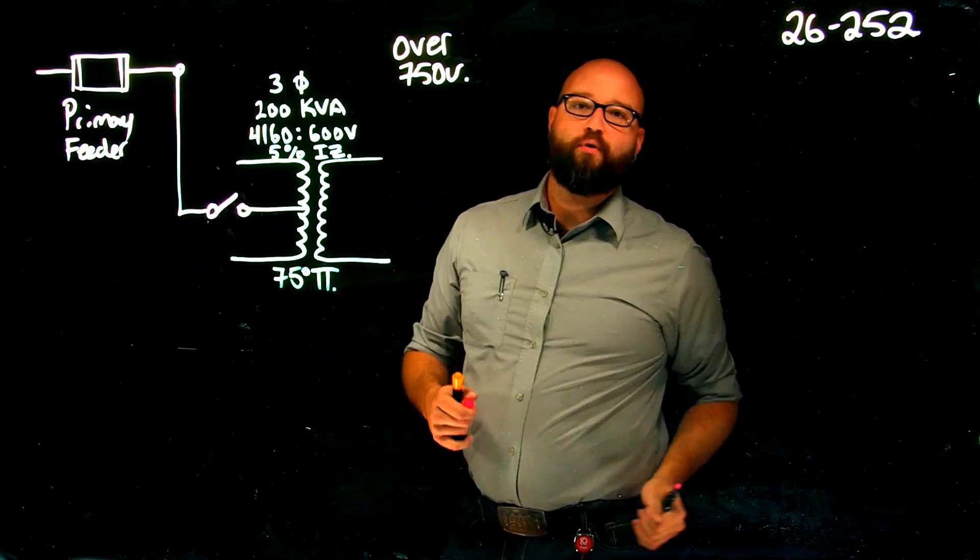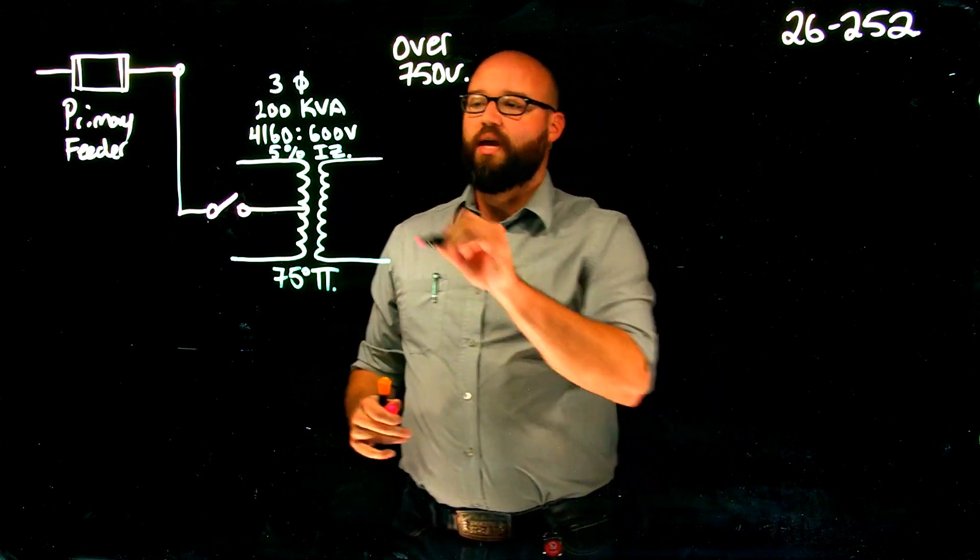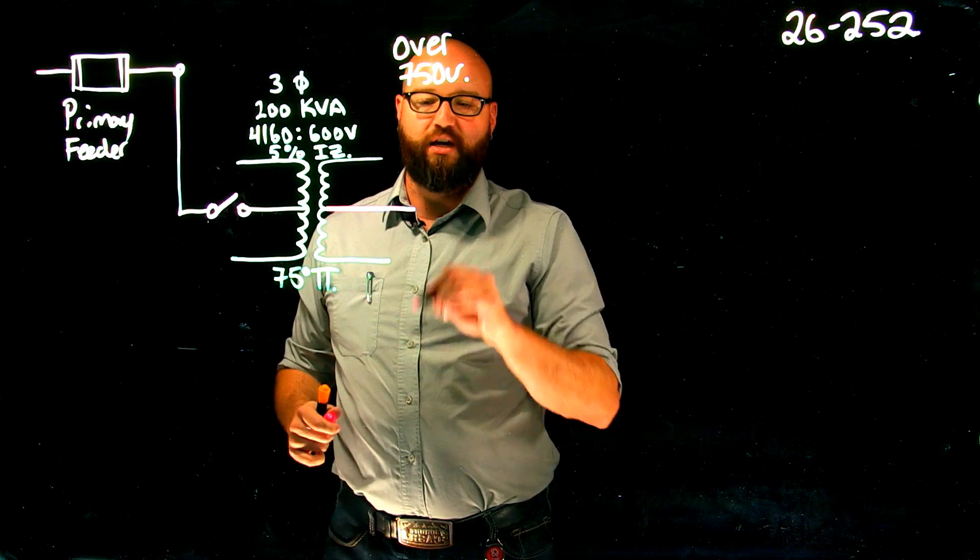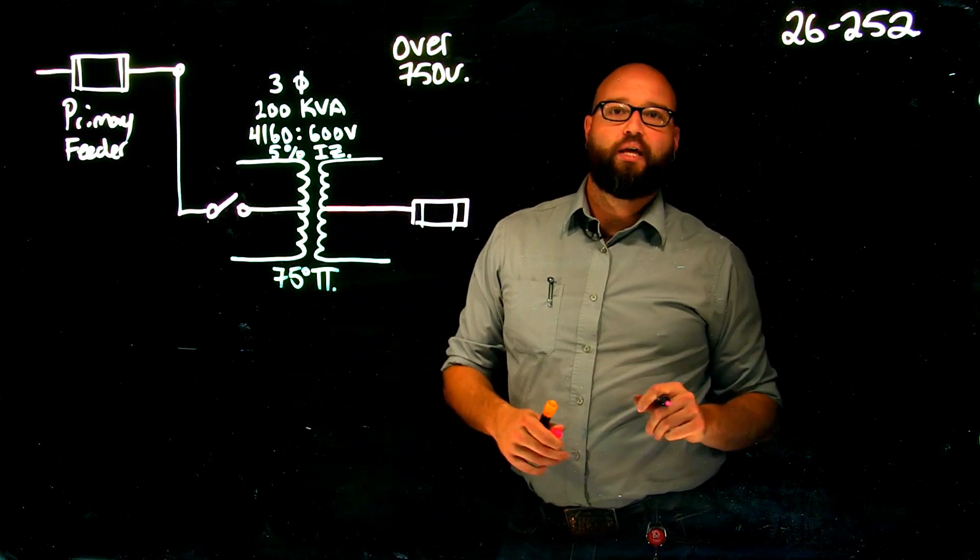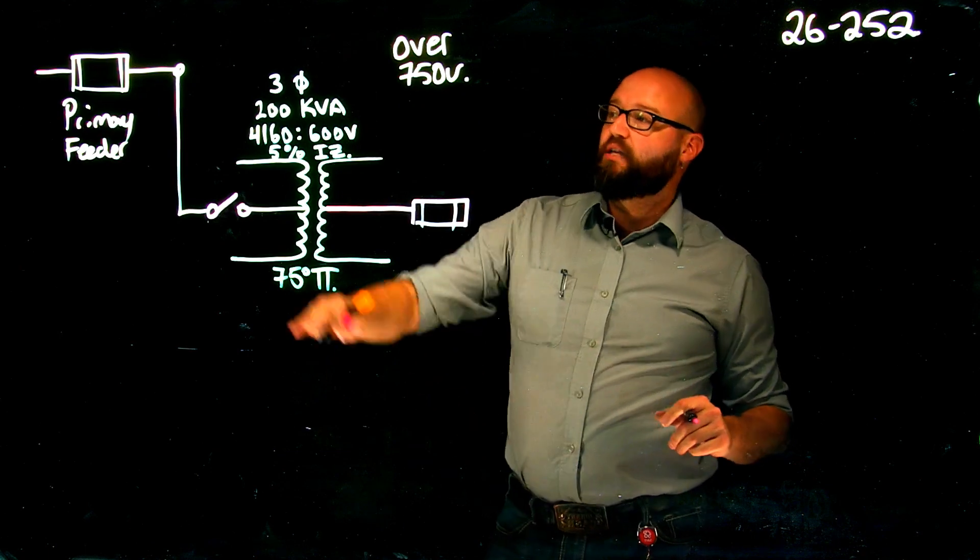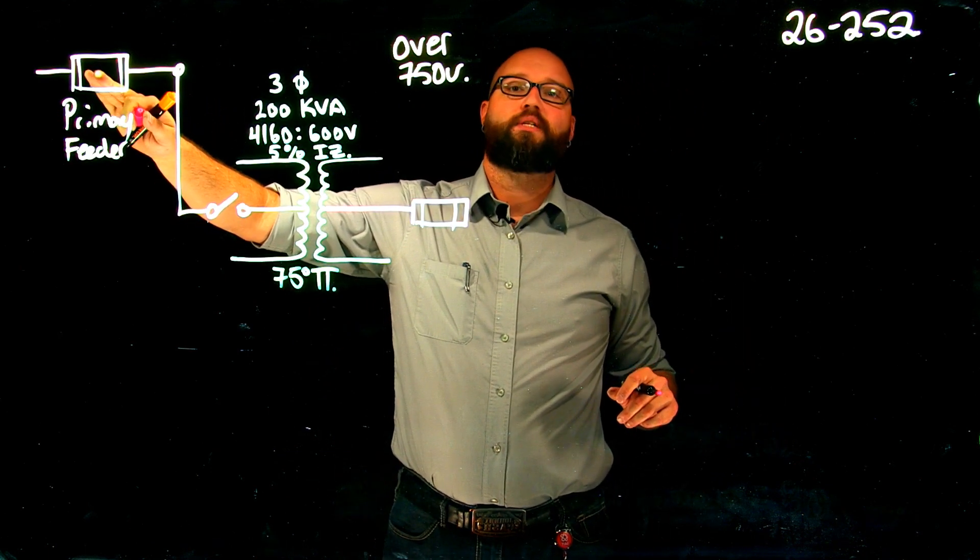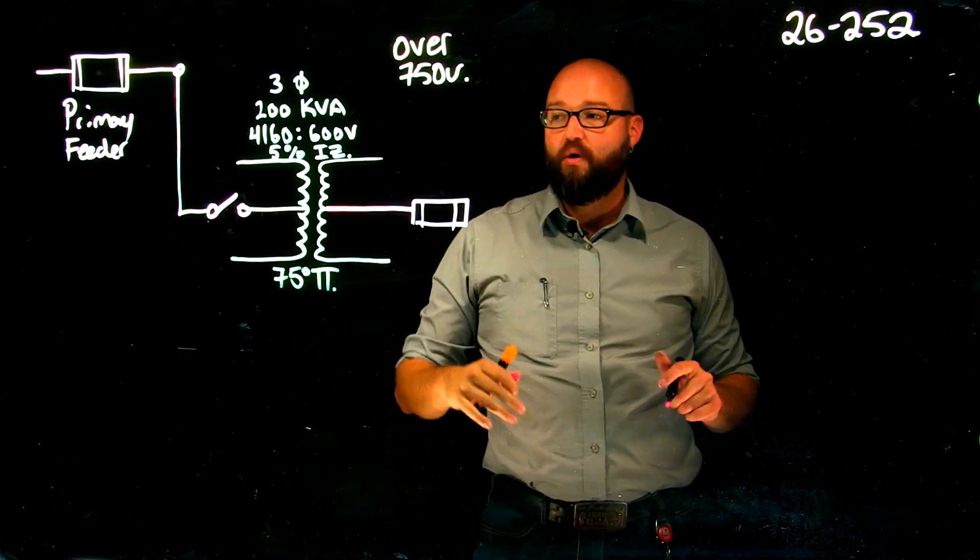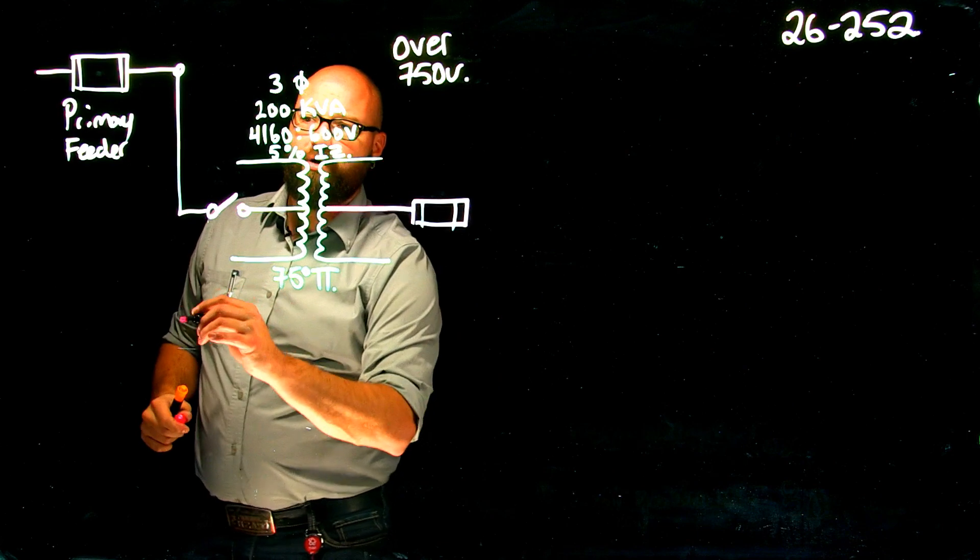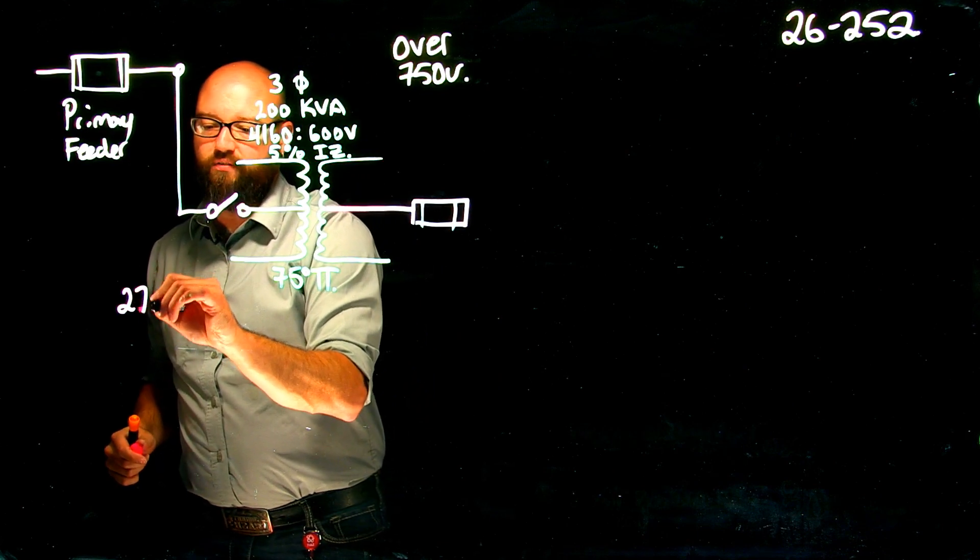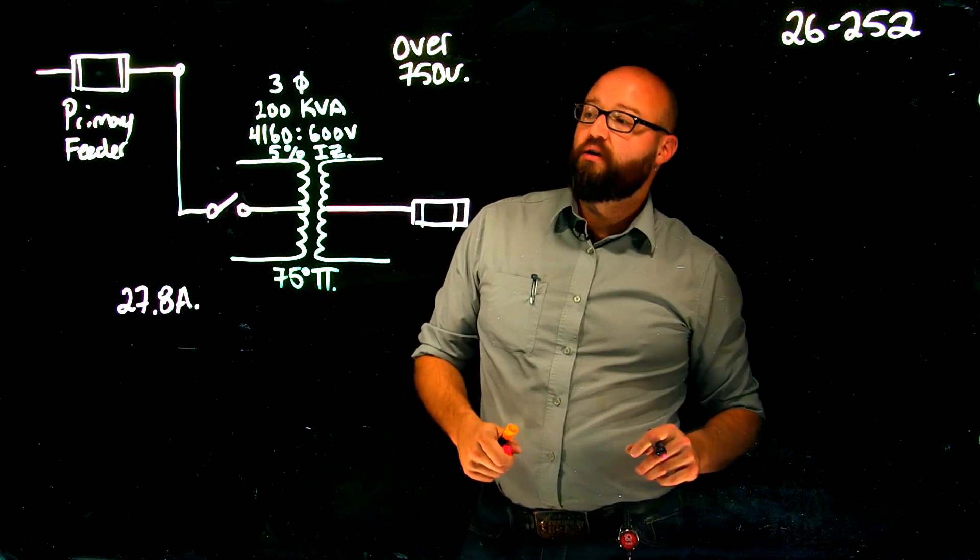Let's look at what happens when we have omitted primary protection in our transformer. 26-252 sub-rule 3 and 4 tell me it's not necessary to have primary protection as long as we have secondary protection rated at values calculated from table 50, as well as primary feeder protection calculated from table 50. We've already calculated that our primary rated current is 27.8 amps, because we will still need to know that number.